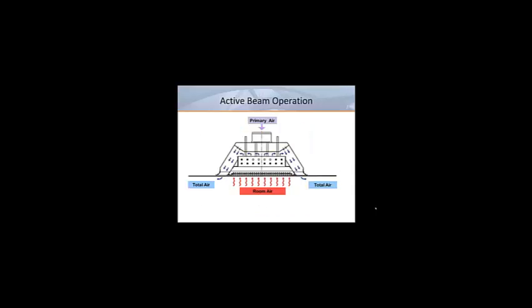Cool and dry air typically 63 to 68 degrees is supplied to the internal plenum of an active beam. This primary air discharges through a series of nozzles creating entrainment. As the room air is entrained by the discharged jet of the active beam, this induced air is drawn up and through the beam where it mixes with the primary air and is then discharged into the room.